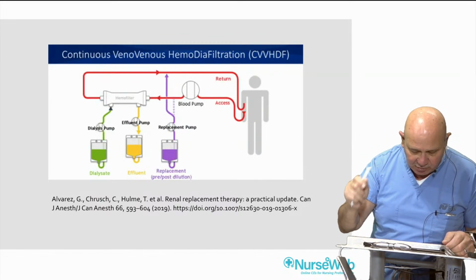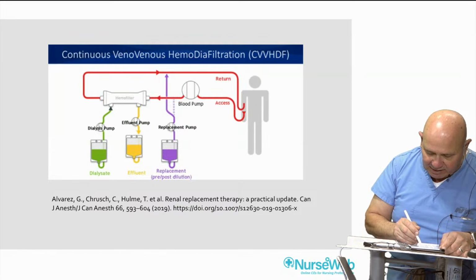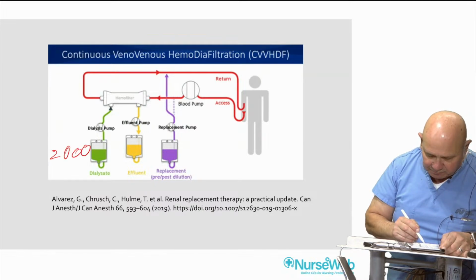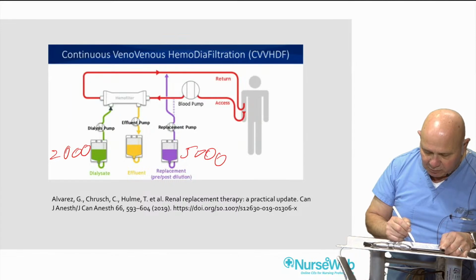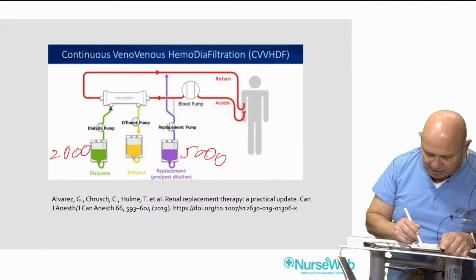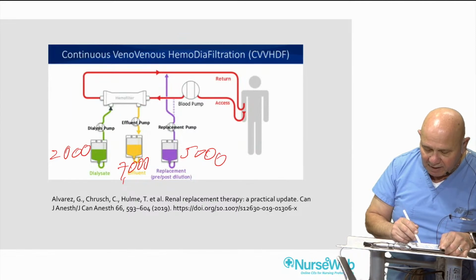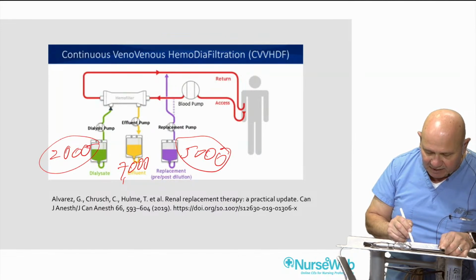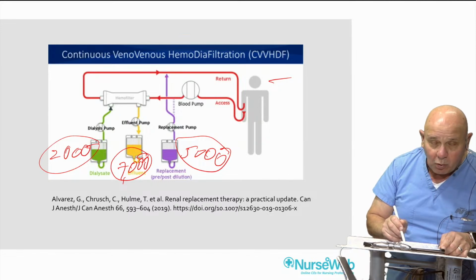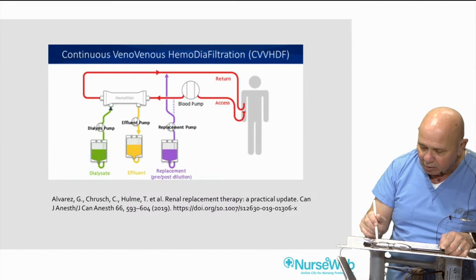And not unlike what I told you earlier, if I'm running 2 liters of dialysate and I'm running 5 liters of replacement fluid, this effluent pump, there has to be 7 liters. But I can't remove that much fluid from the patient, because then there would be 2 liters patient negative. And again, the way these machines are designed, it's going to understand this pump is at 2 liters, this is at 5 liters. It's going to take 7 liters, but it's not going to have the patient volume be negative, nor, as it cannot do, be positive. It just can't do that at all.